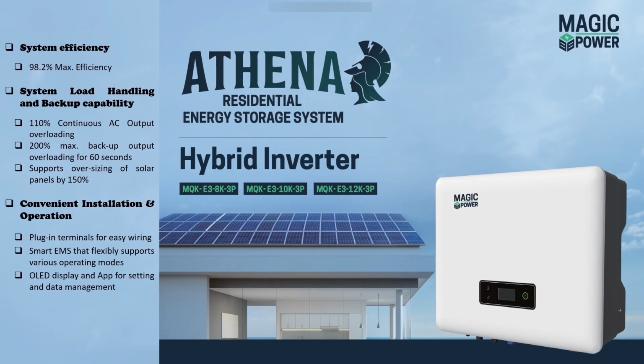The high voltage energy storage system is called the Athena series. The rated output power for the system is 8 kilowatts, 10 kilowatts, and 12 kilowatts. If you look at the key features, the system efficiency is 98.2%. Okay, load handling and backup capability: 110% continuous AC output overloading, and 200% maximum backup output overloading for 60 seconds.